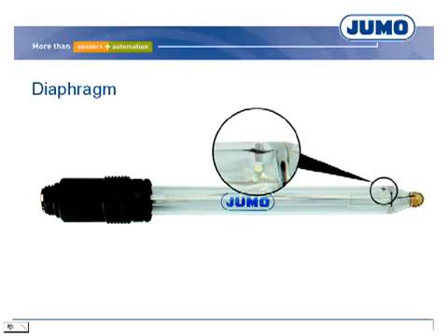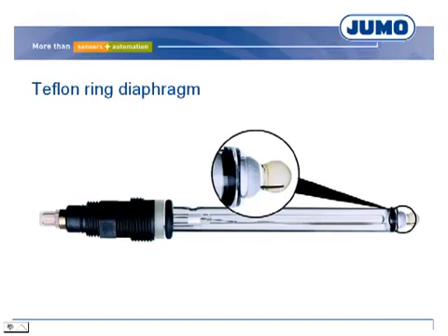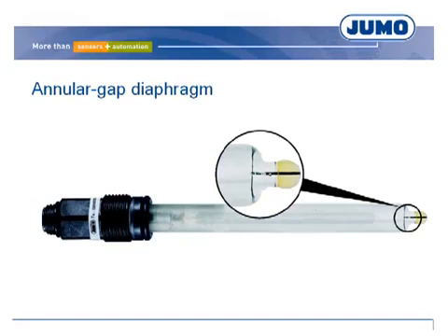The ceramic diaphragm can be used for measurement in clean solutions like drinking water and swimming pools. For heavily polluted water such as wastewater, a Teflon ring diaphragm is used, or open diaphragms like annular gap or perforated diaphragm.